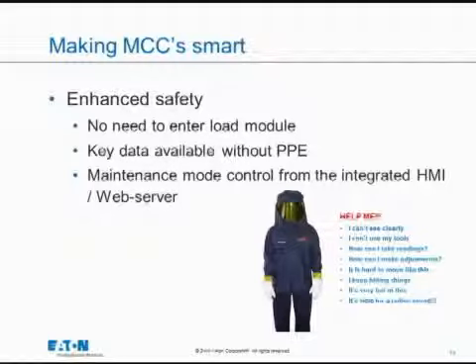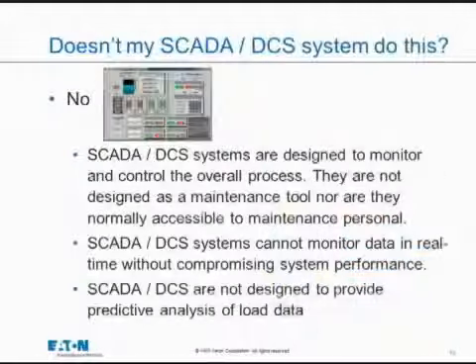So one question that always comes up is, I have a SCADA system, why can't it do that? Well, SCADA systems are designed for the process. Their job is to deal with the whole process, not the individual element. Where you might be talking about one motor in a smart MCC, he's dealing with a hundred motors, thousands of sensors, heaters, pressure transducers, whatever. That's what the SCADA system is designed to do: the process, the tension loops, all the recipes. It has no time to deal with maintenance issues.